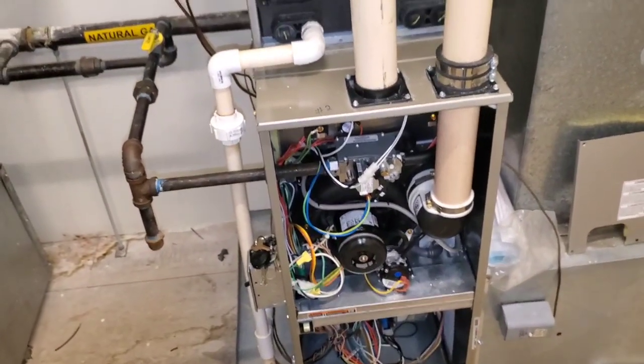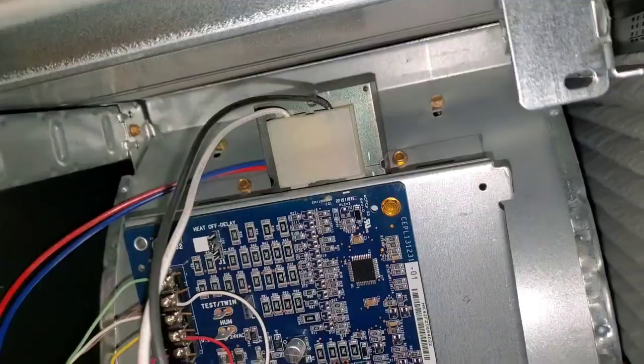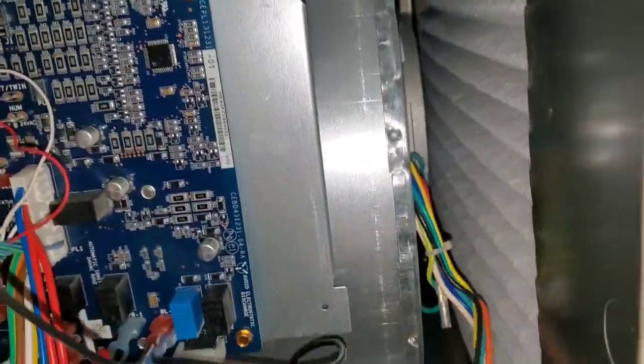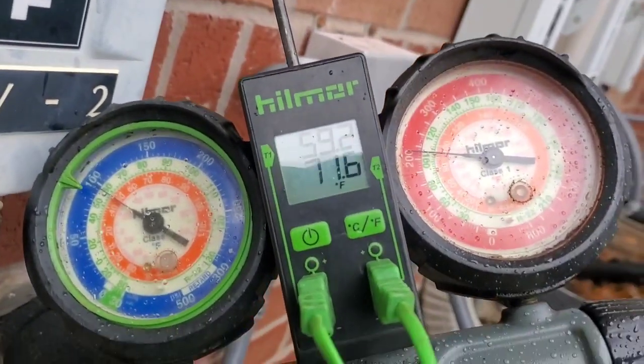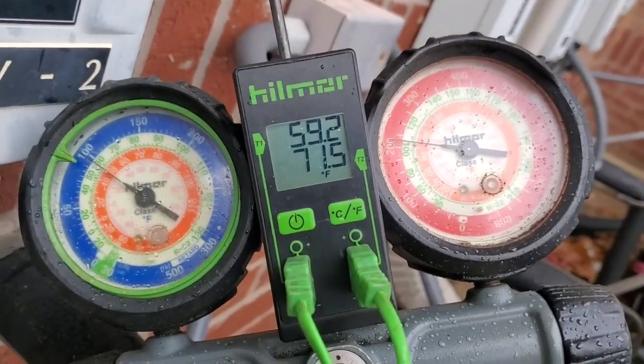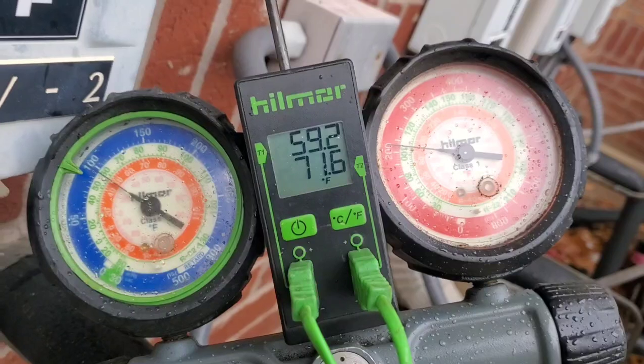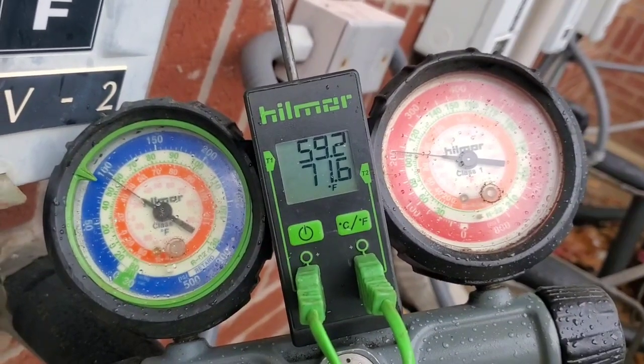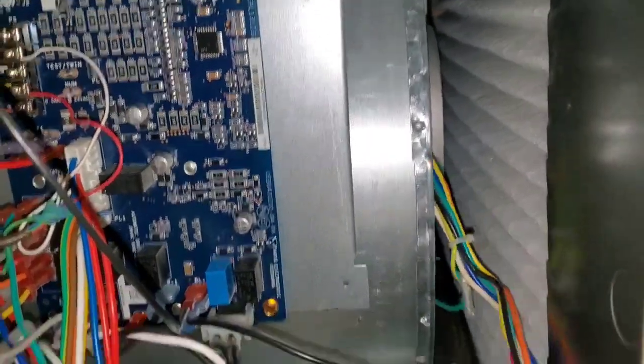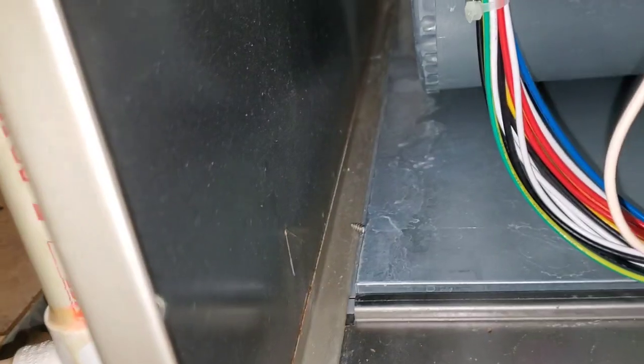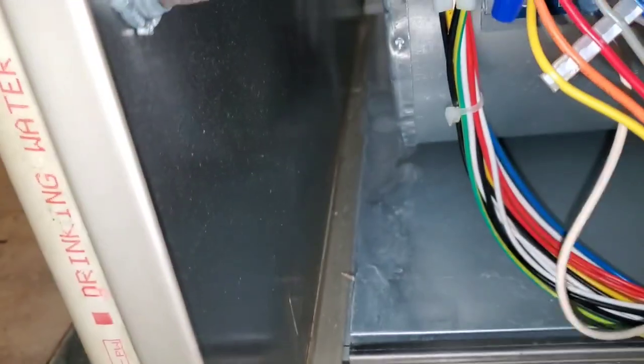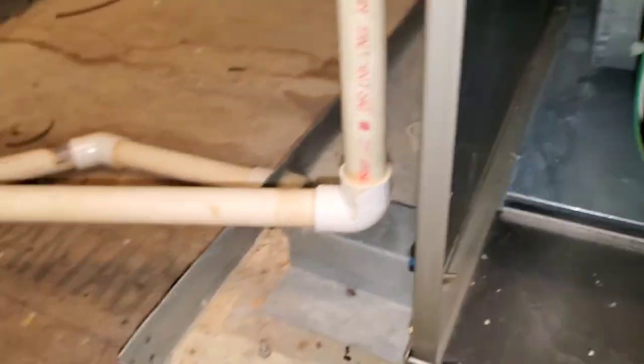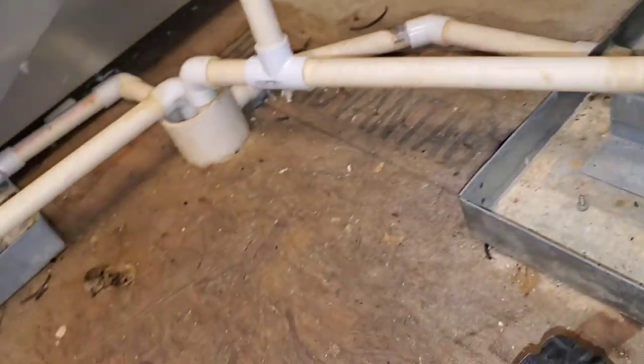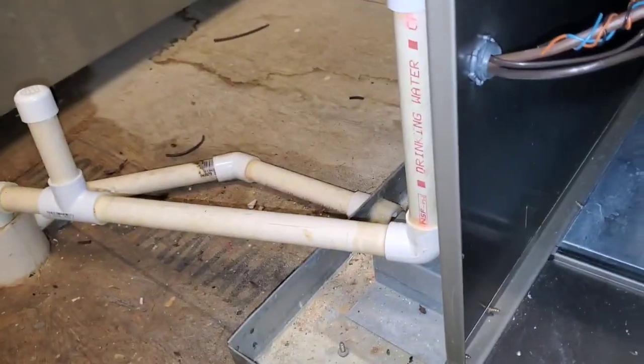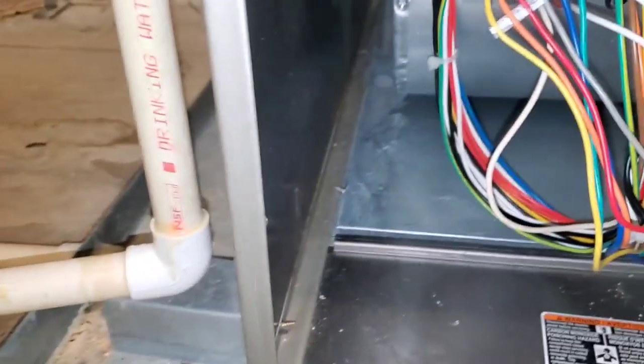What do you do about this here? You spray CalGuard on the board. None of that. So we got 30 degrees of subcooling and no superheat. There's a little bit of water stains down here, but it's all dry still. Of course, they turned it off, so the water's all dried up now.